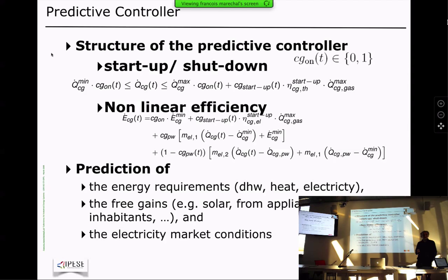If I'm starting, there is an energy consumption involved. This means that if the unit is shut down, it cools down, and the mass of the unit reduces its temperature. So when I start the unit again, the first part of the energy spent will be to heat the equipment itself, and this corresponds to an energy consumption that has to be accounted for.